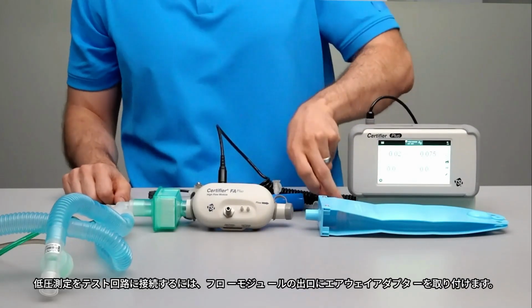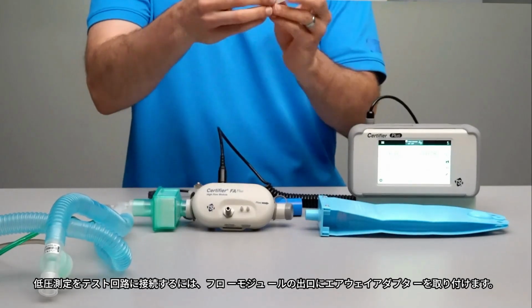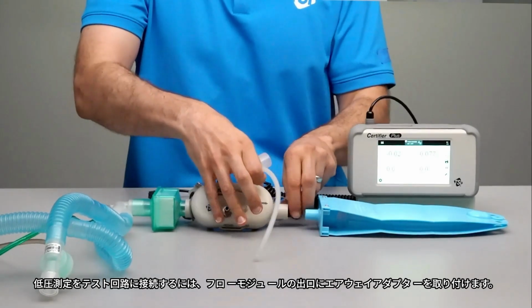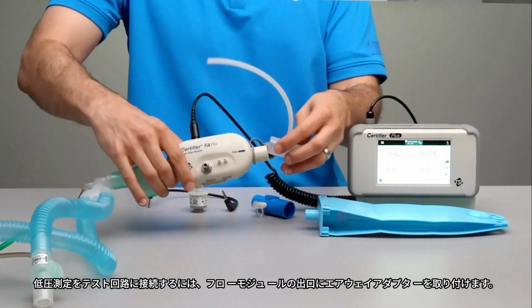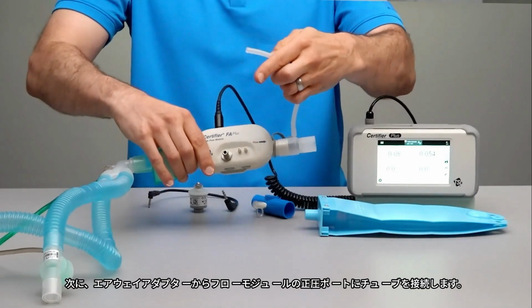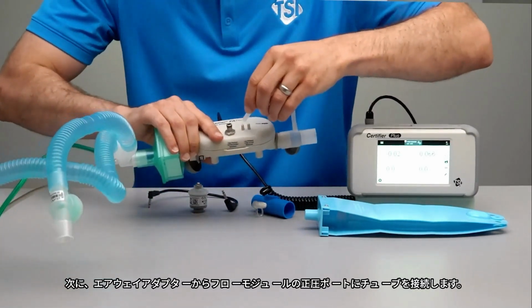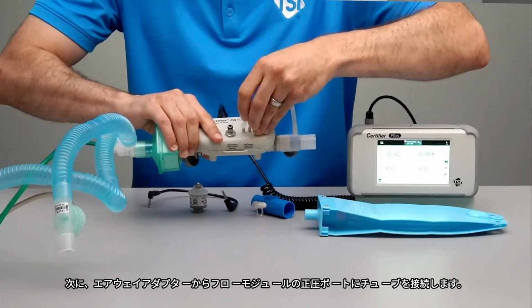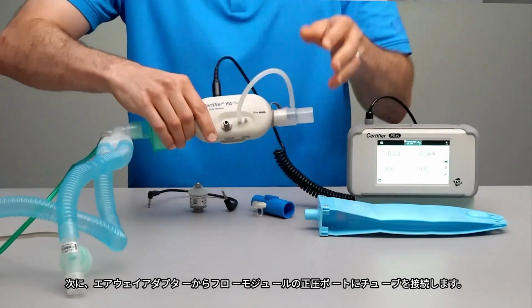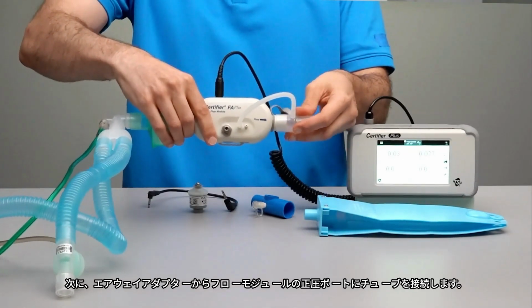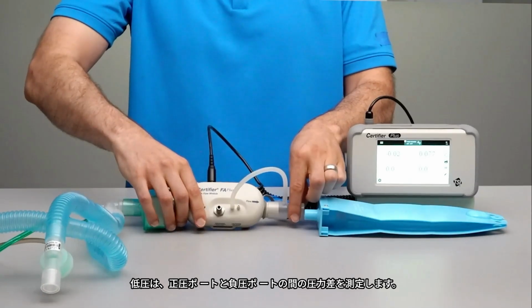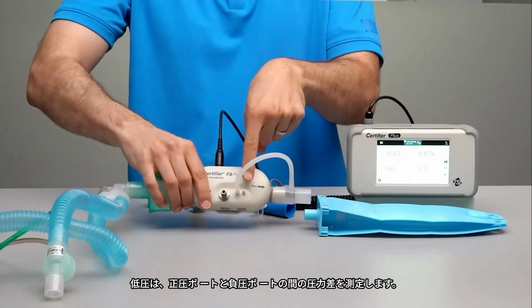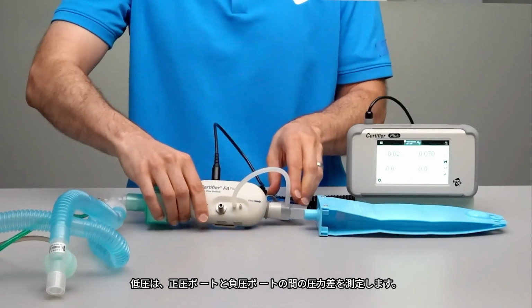To connect the low pressure measurement to the test circuit, attach the airway adapter to the outlet of the flow module and then connect a piece of tubing from the airway adapter to the positive pressure port on the flow module. Low pressure measures the difference in pressure between the positive and negative ports.